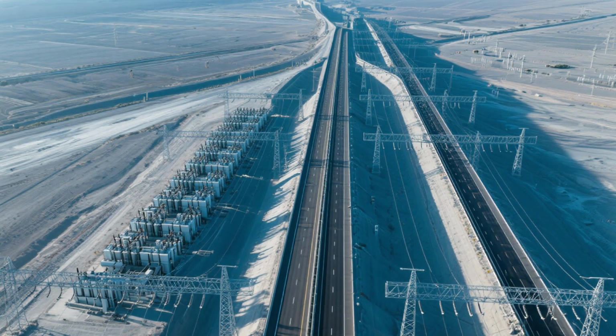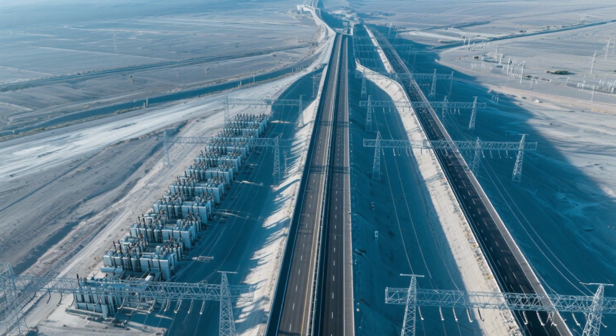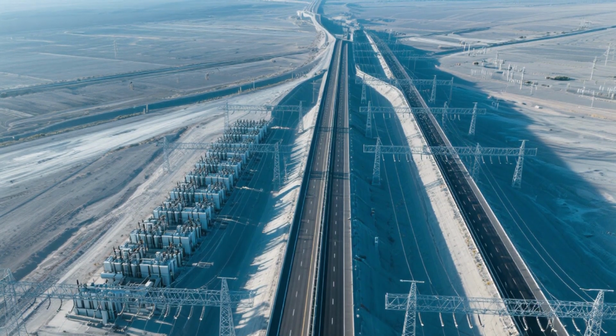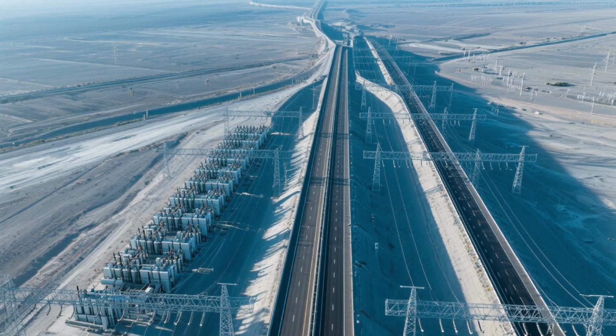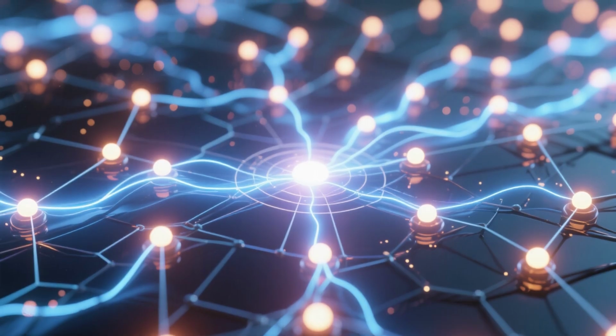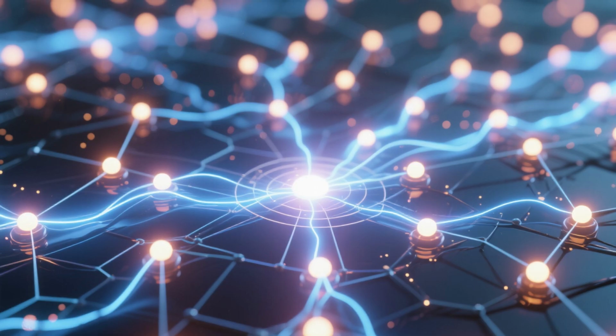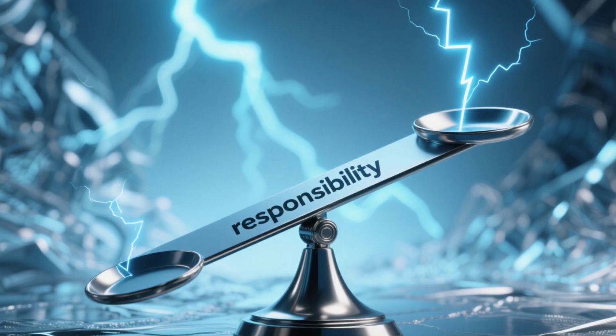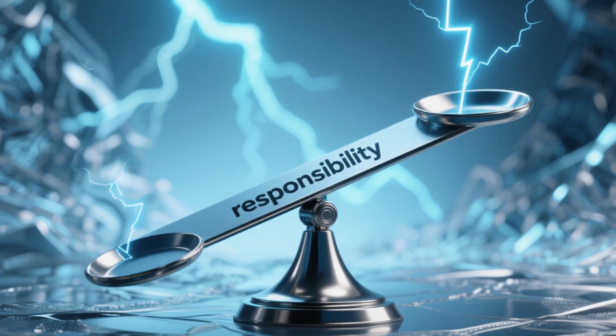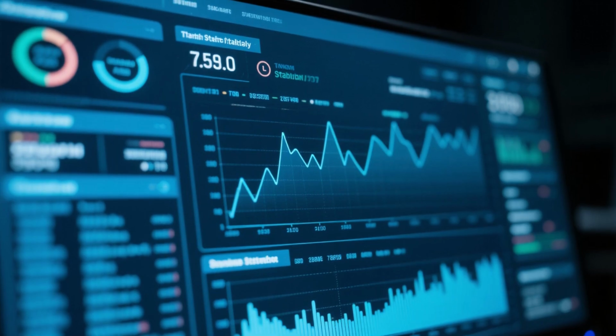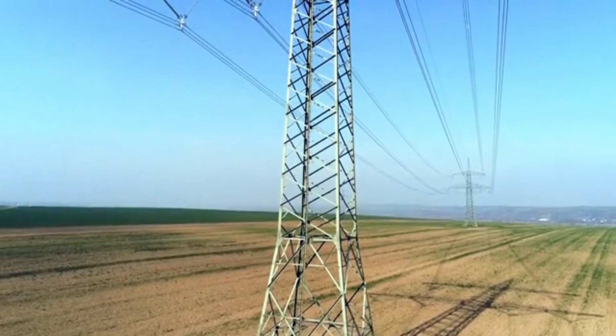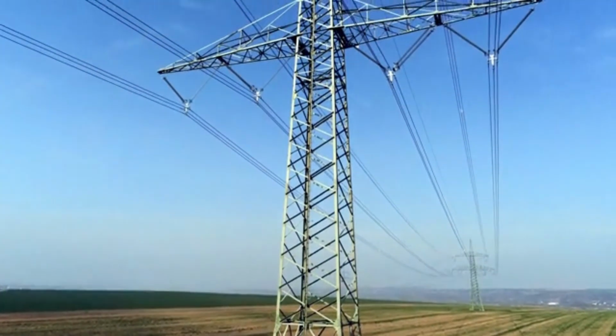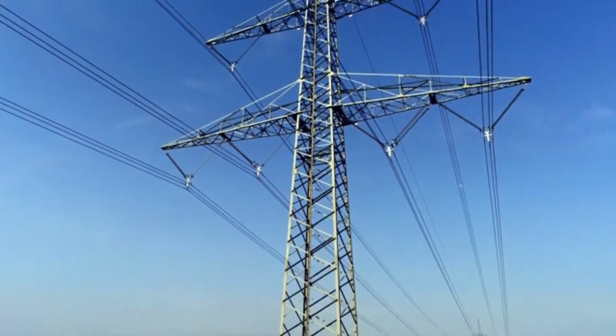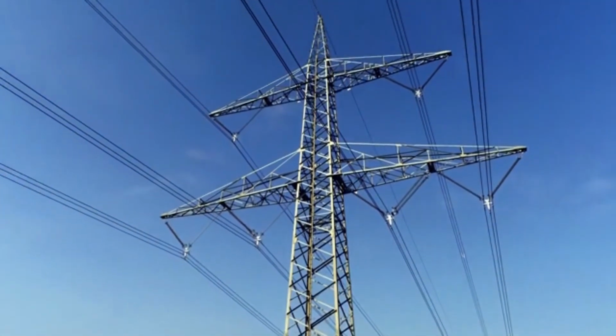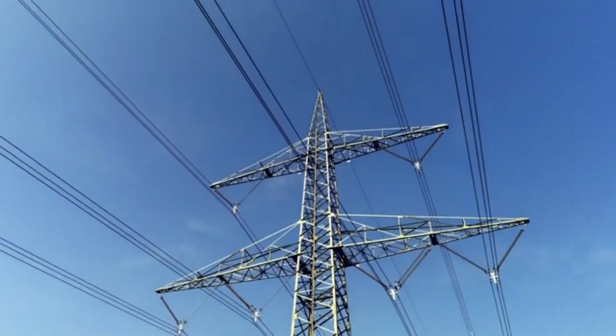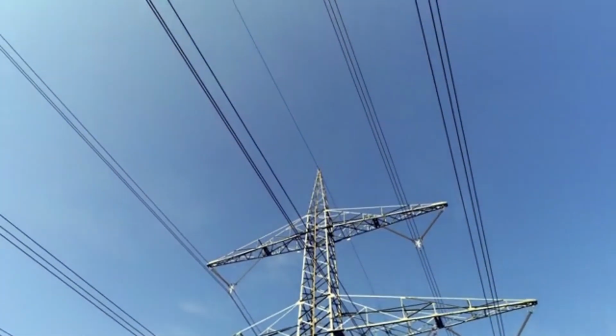MT-HVDC systems are the superhighways that make this possible, transmitting vast amounts of power over long distances with remarkable efficiency. They connect multiple points, creating a flexible and robust power network. But with great power comes great responsibility. The stability of these complex networks is paramount. A single fault, like a short circuit on a transmission line, can trigger a cascade of failures, potentially leading to widespread blackouts, if not handled immediately.